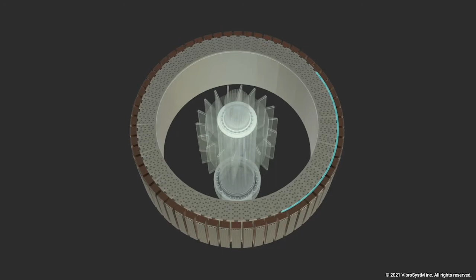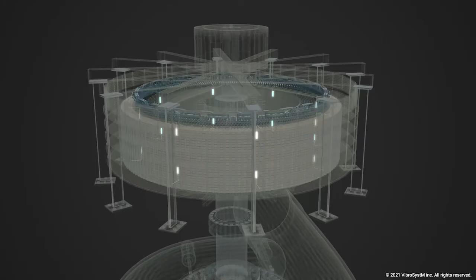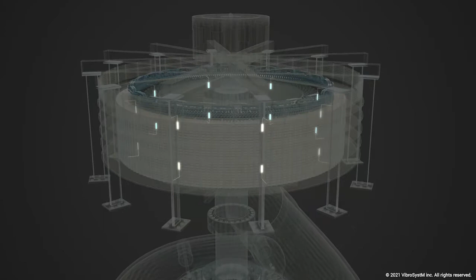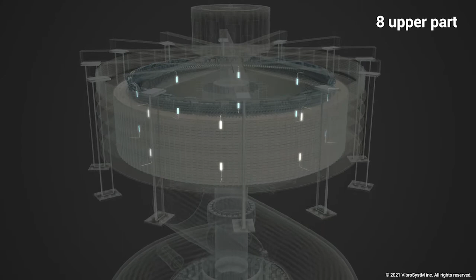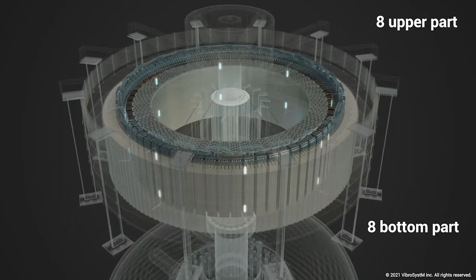The utility accepted the bid on the condition that the OEM would be able to validate or confirm the performance of the rotor rim to make sure it performed as designed. To do so, they installed 16 airgap sensors on all 4 units, 8 at the upper part and 8 at the bottom part, to look at the rotor and see how it behaves during overspeeds. When I got there for this particular visit, they had done some initial testing, and that was prior to the commissioning.